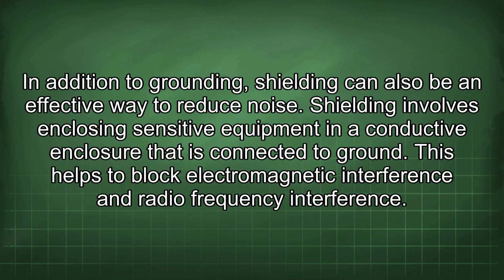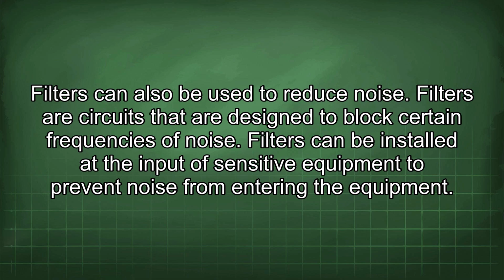In addition to grounding, shielding can also be an effective way to reduce noise. Shielding involves enclosing sensitive equipment in a conductive enclosure that is connected to ground. This helps to block electromagnetic interference and radio frequency interference. Filters can also be used to reduce noise. Filters are circuits that are designed to block certain frequencies of noise. Filters can be installed at the input of sensitive equipment to prevent noise from entering the equipment.